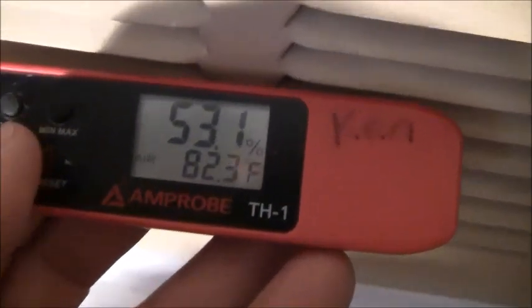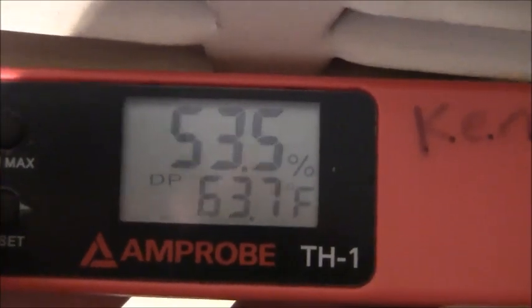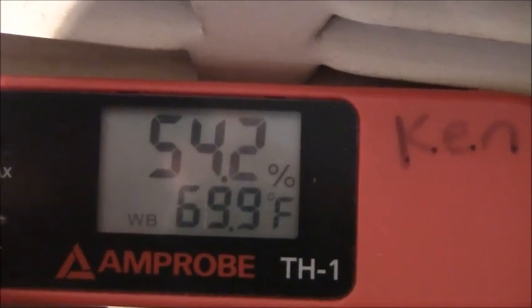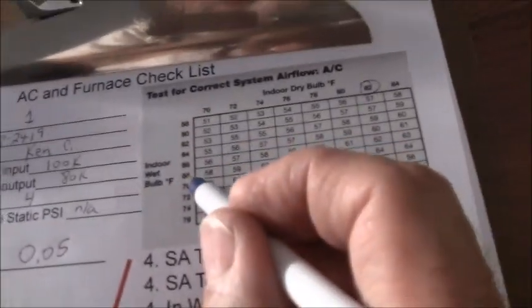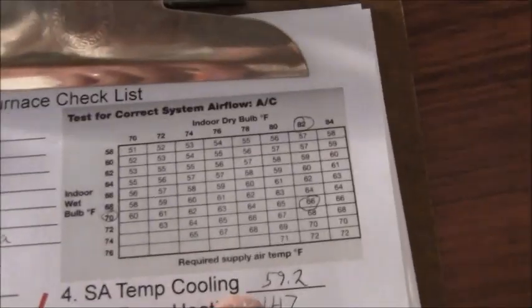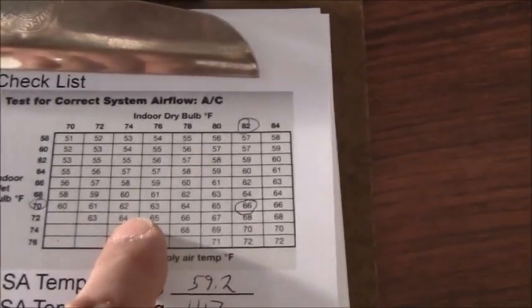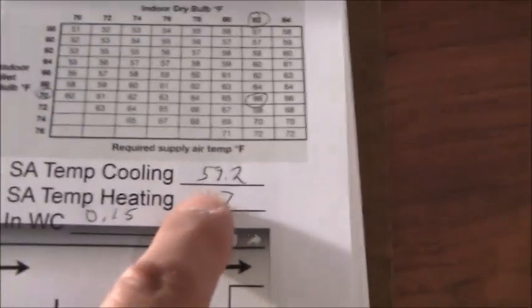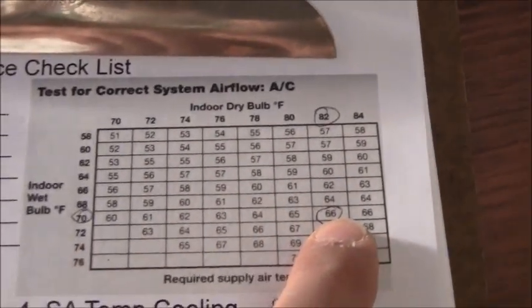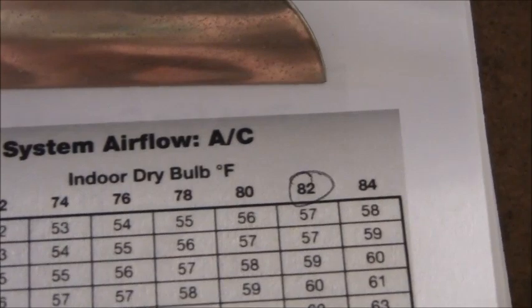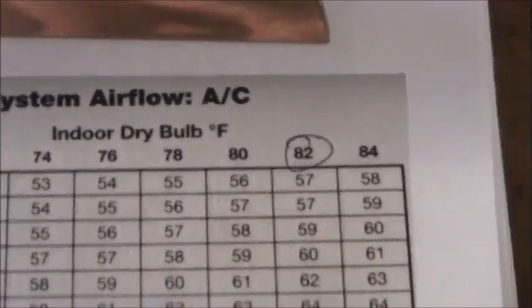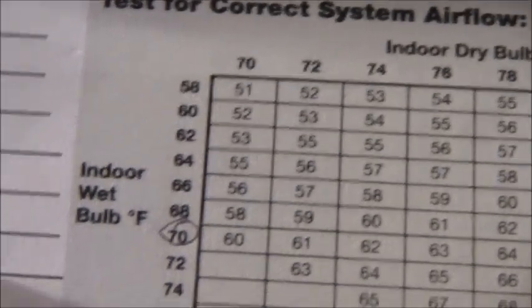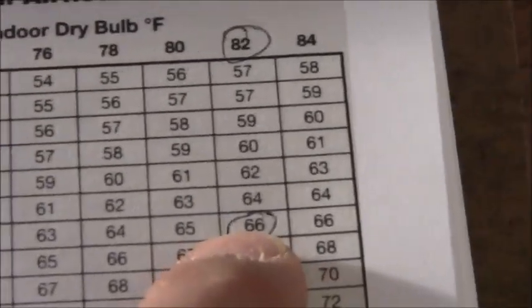Hit the mode button here. .9, call it 70. Okay, so now I'm going to go to 70. The supply air temperature is at 59. This is telling me, according to the chart, which you go from the dry bulb temperature, 82, bring that down, match that up with the wet bulb temperature of 70, it's saying it wants a supply air temperature of 66, okay?